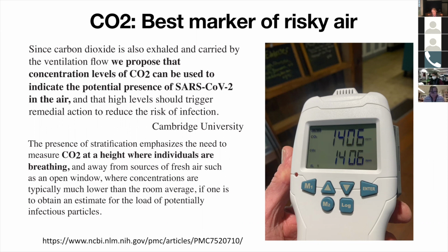The presence of stratification emphasizes the need to measure CO2 at the height where individuals are breathing. And that's why when we came into your classrooms, we tried to have the meters right about student level and away from sources of fresh air, where concentrations are typically much lower than the room average.